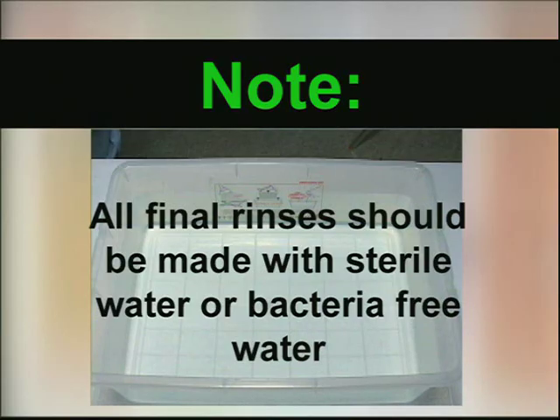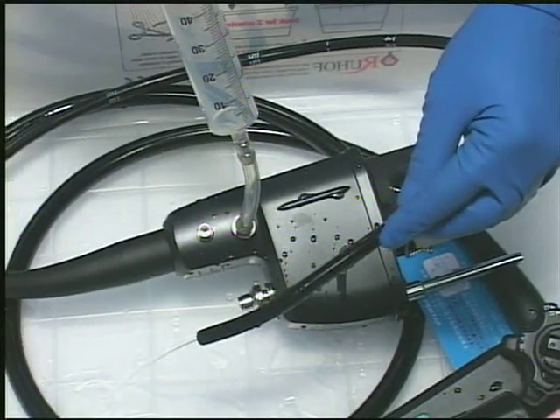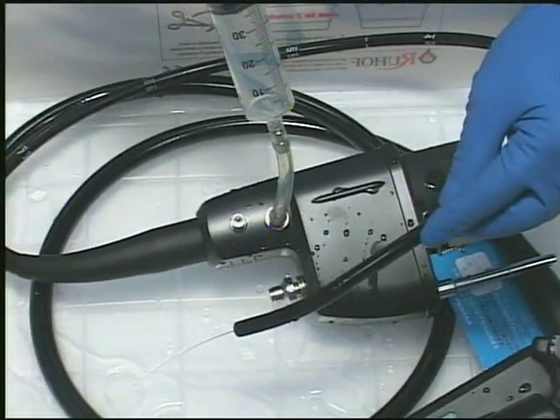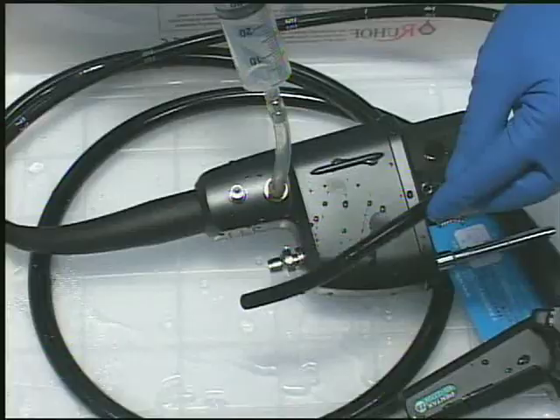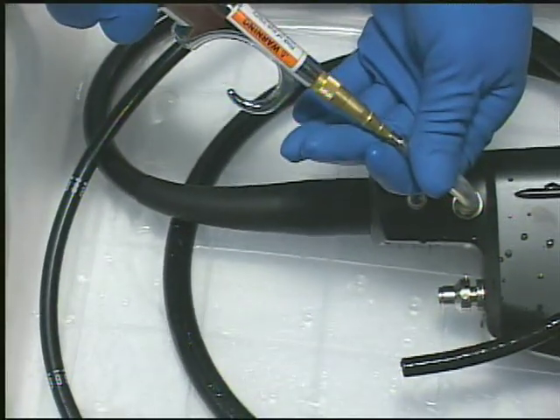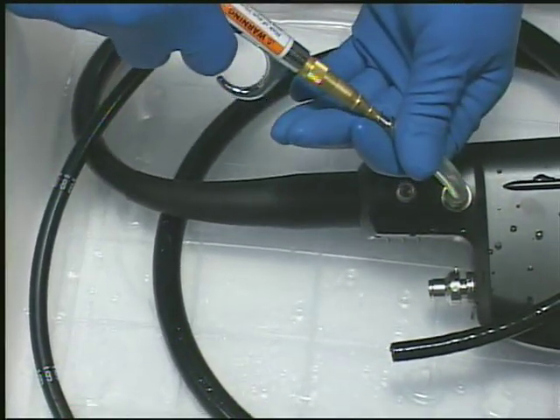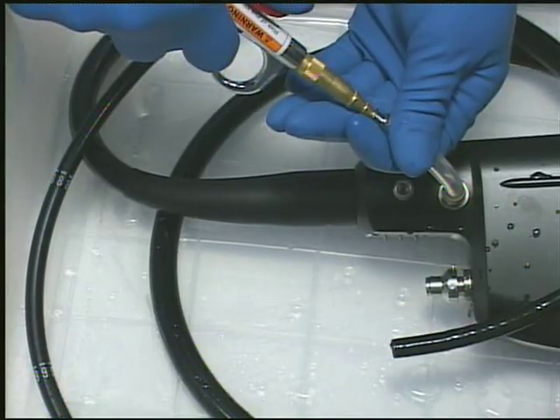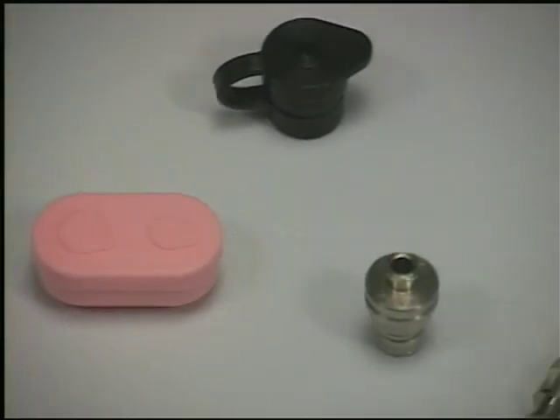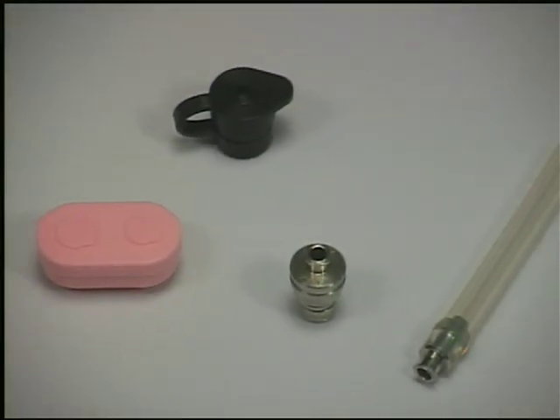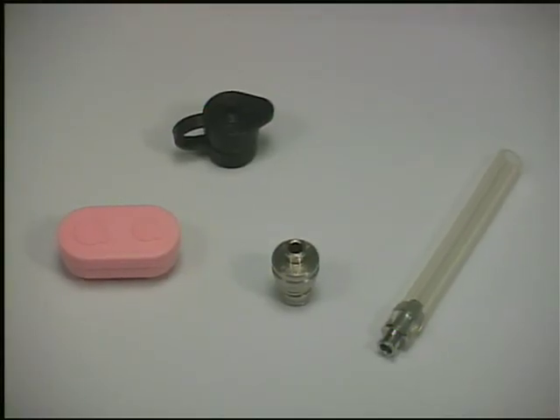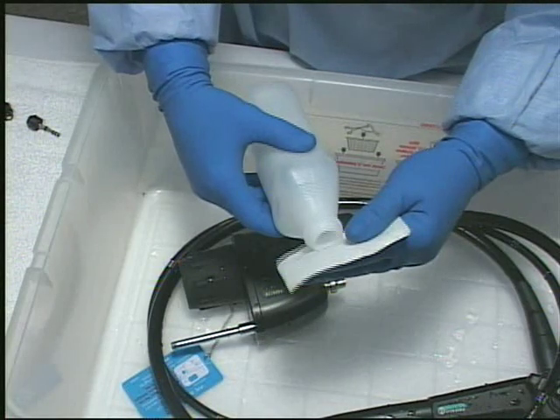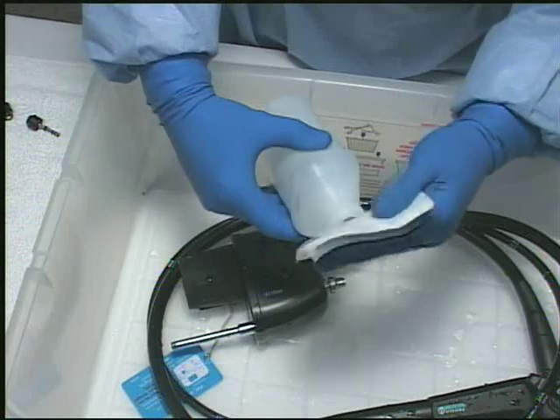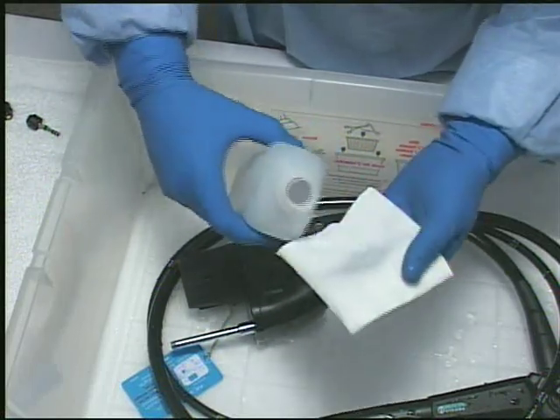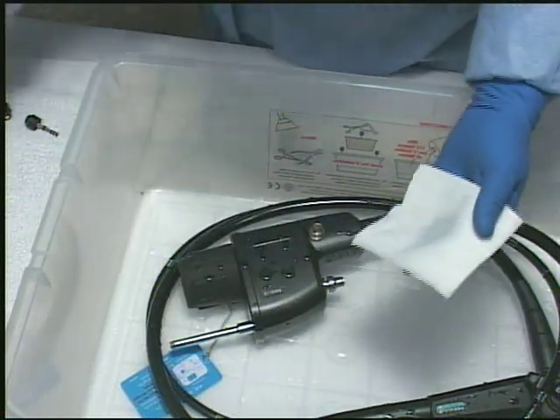After water rinsing, 70% alcohol should then be flushed through all channels, followed by compressed air not greater than 24 psi to facilitate drying. Channel cleaning adapters should be used for alcohol flushing or rinsing and forced air drying. The outer surfaces of the endoscopes can be dried by gently wiping with a gauze or lint-free cloth saturated with alcohol.